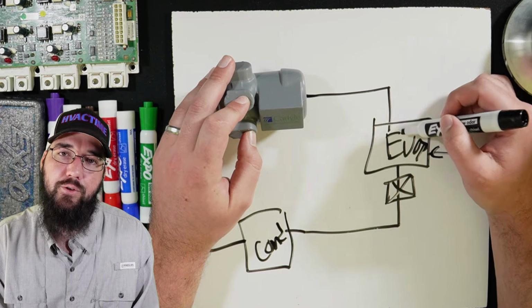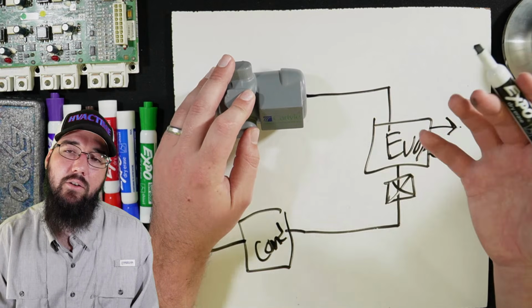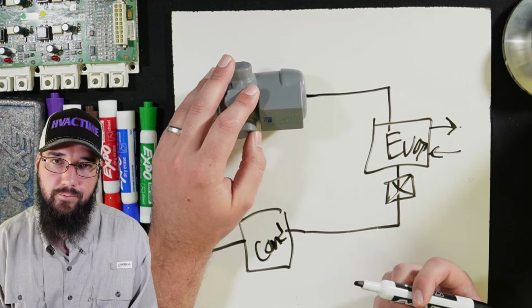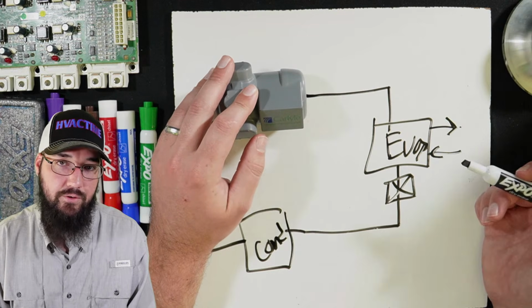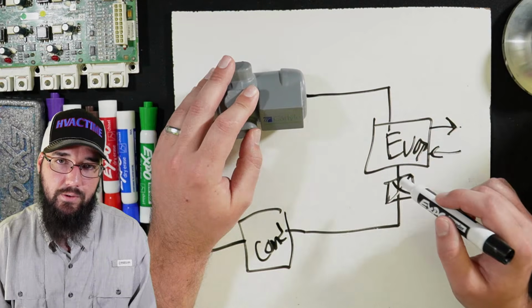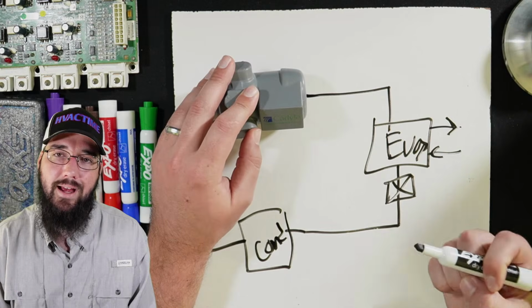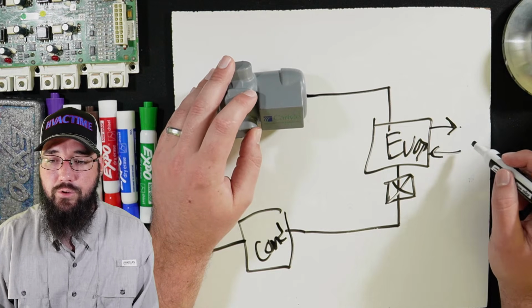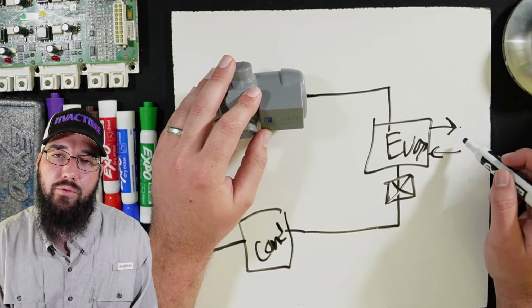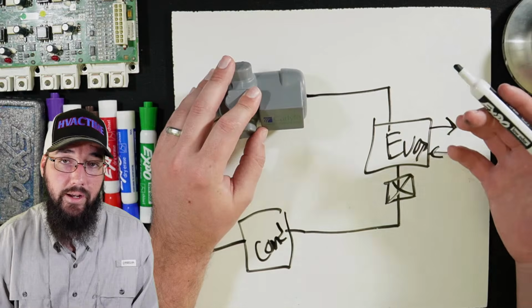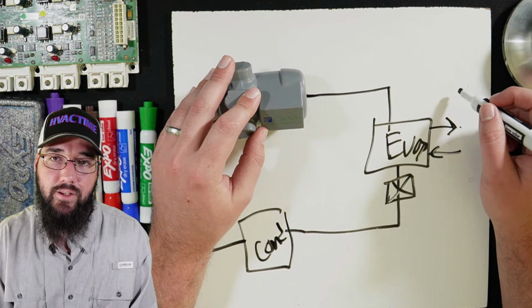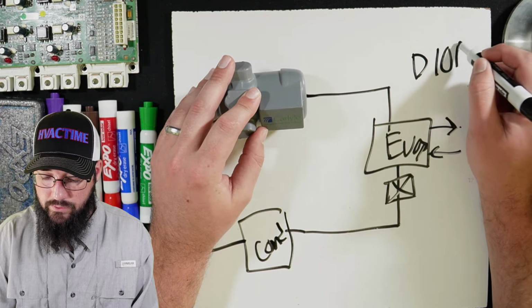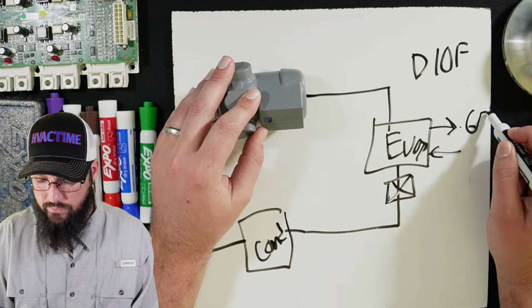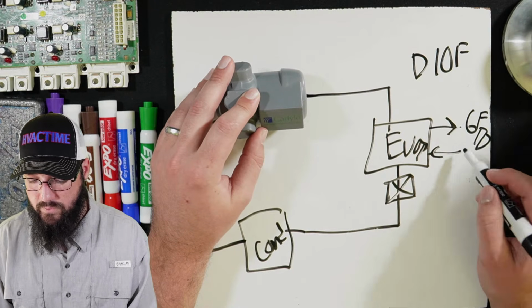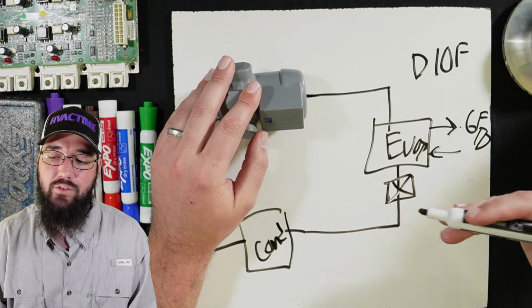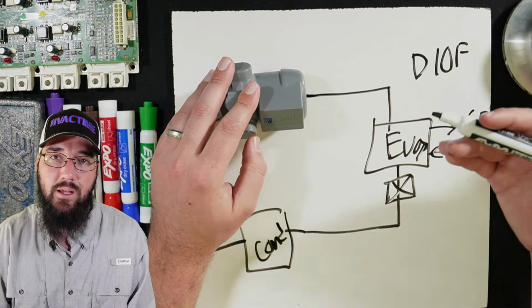We have less refrigerant moving through the evaporator. Because of that, we're not pulling down on the saturation temperature as hard. Now, we do end up feeding less refrigerant as well, so there is a balancing act that happens here, but ultimately, we're not drawing down on the evaporator as hard. At the same time, we do have less heat being moved through this evaporator because we're at an unloaded state. So let's say our design was 10 degrees Fahrenheit, but we're only moving 6 degrees Fahrenheit as our actual TD through this evaporator. So now we have less total heat that we need to remove in order to achieve set point.